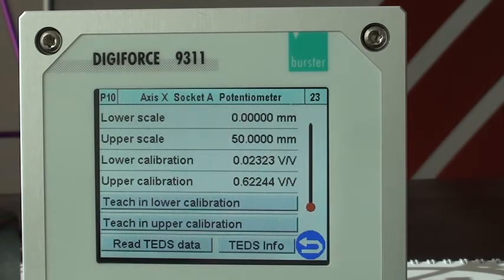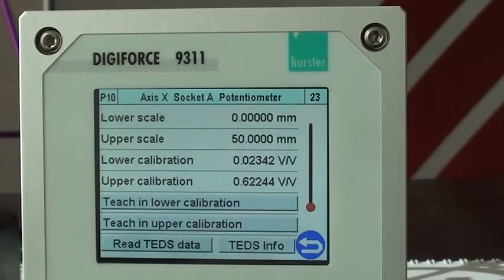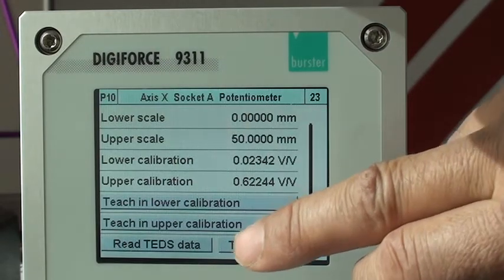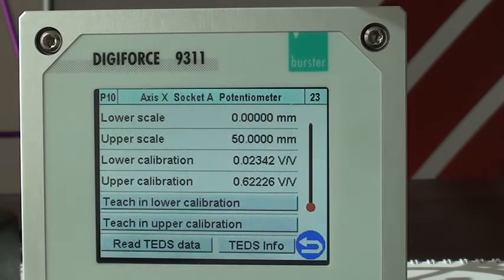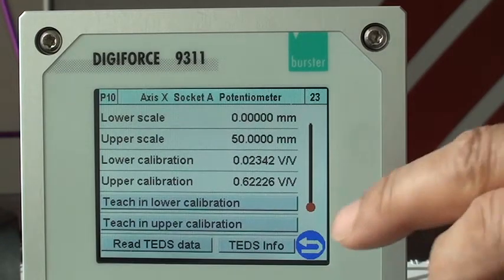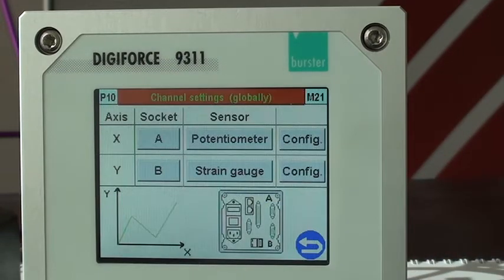With your device set at the lower calibration position, select Teach in Lower Calibration. The 9311 will measure and input the data in the lower calibration. Move your sensor to the upper calibration position. Select Teach in Upper Calibration. The 9311 will measure and put in the upper calibration numbers into the unit. Press Return. We're going to configure the Y channel or strain gauge.